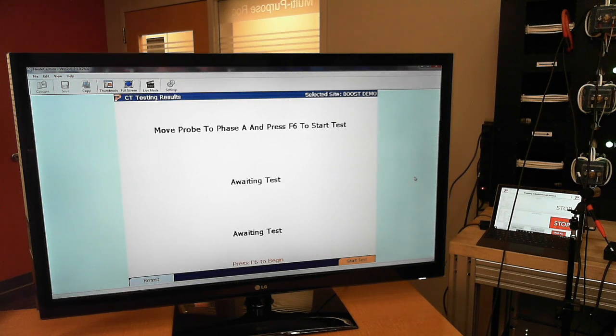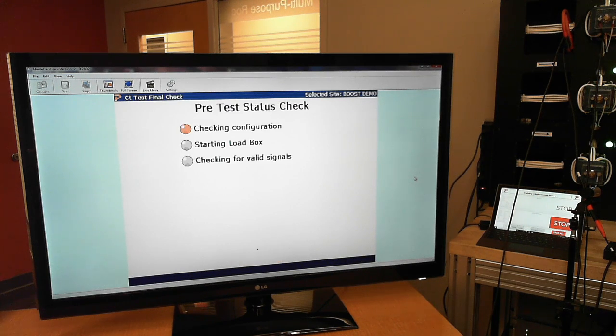I've got the probe on phase A. When you only use one probe, it always gives you that screen where it says move probe to phase A and hit F6. When you're done with phase A, it's going to tell you move probe to phase B and hit F6.